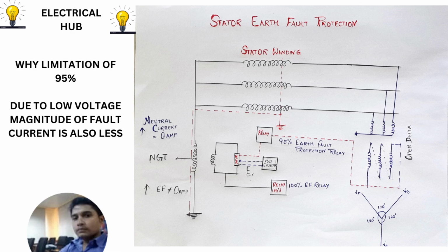The question comes, why will this 5% of the winding not be protected? This 5% of the winding will not be protected because of the low voltage magnitude in this region. If any fault occurs, then low current will pass through the neutral grounding transformer, and similarly low current will be induced in the secondary, and there will be a very low voltage drop across the NGR. Maybe the relay will not trip.